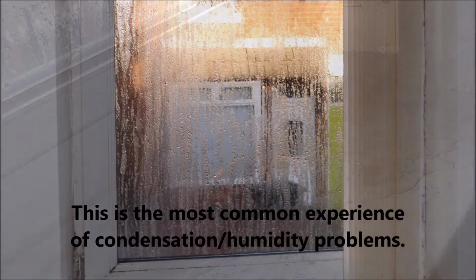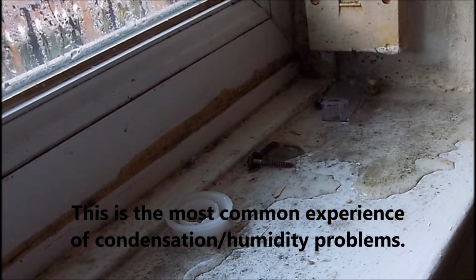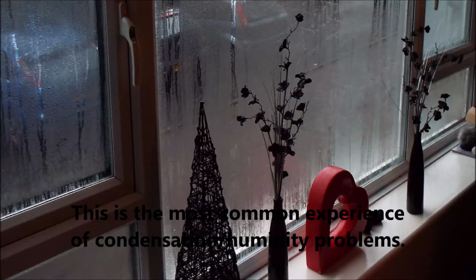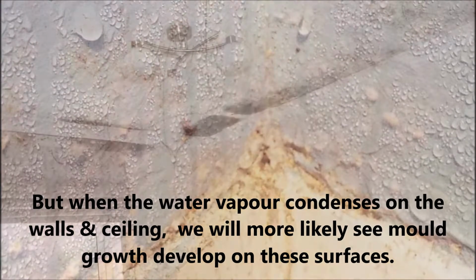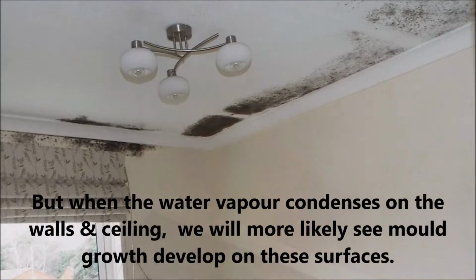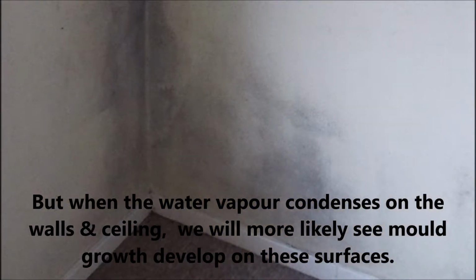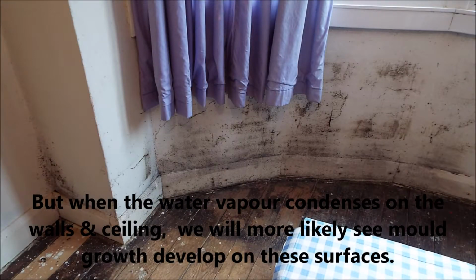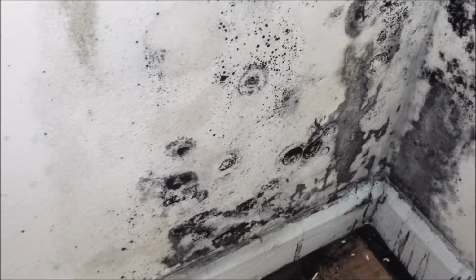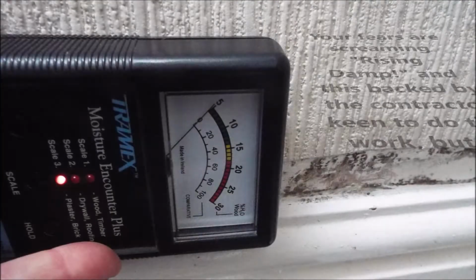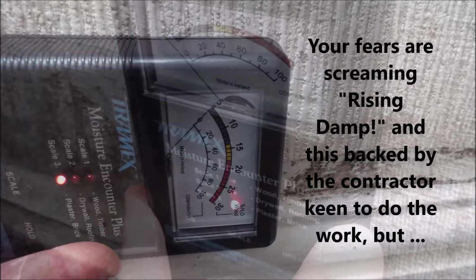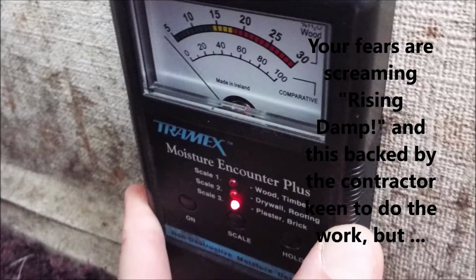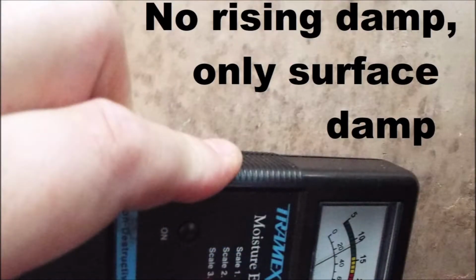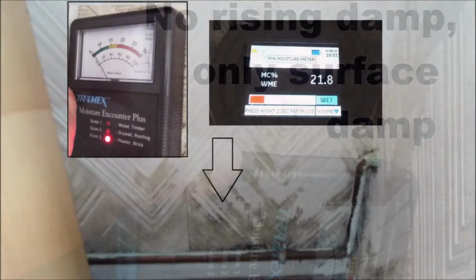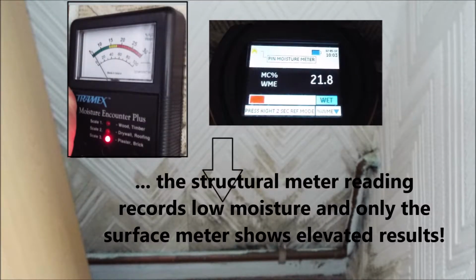It's now that we move into more familiar territory, with condensation forming on windows, but also the window reveals due to cold bridging, as well as on the walls and ceilings. Once again, we check with a variety of meters. There is no structural anomaly with the moisture penetrating or rising into the wall, and here at least we find the walls to be dry, whilst the surface only has elevated moisture levels.